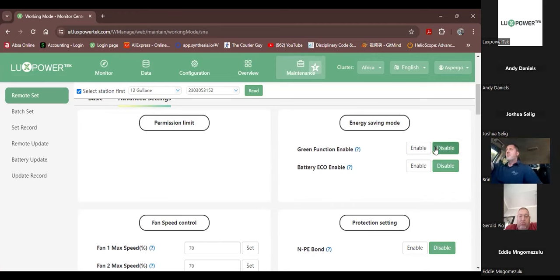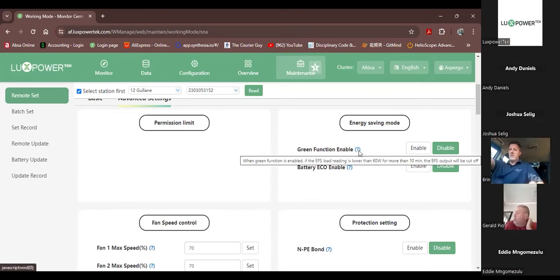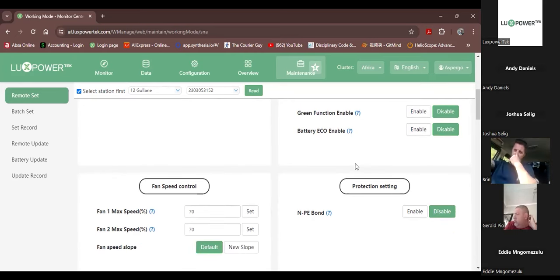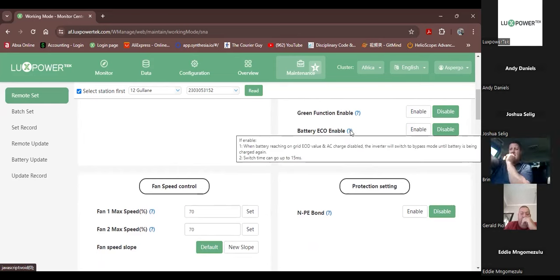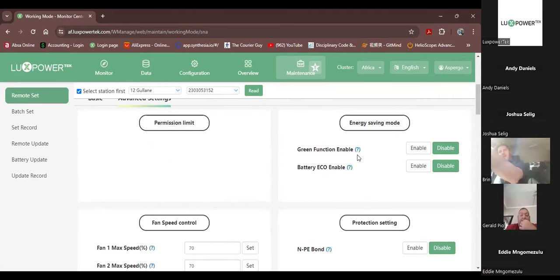So please only enable this function if you've got an installation like a holiday home or something where you want to preserve the battery, and you know the grid is stable, then you can enable the function here. All right, and then same thing with the battery eco enable. If you hover over the mouse there, it basically says when the battery reaches an on-grid end of discharge value and AC charge is disabled, the inverter will switch to bypass mode until the battery is being charged again. And remember that it'll only go to battery charging in the battery charge time that you've allocated, and that the switching time can also take up to 15 milliseconds.